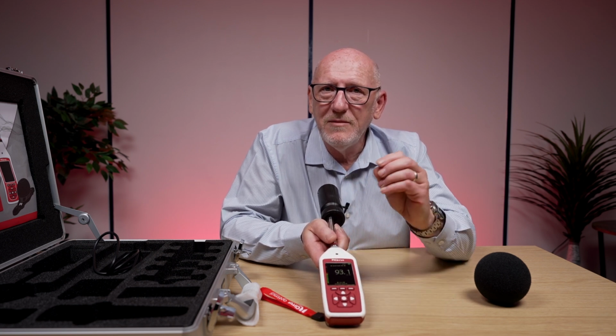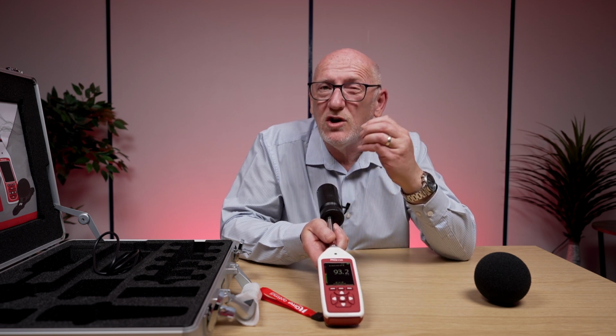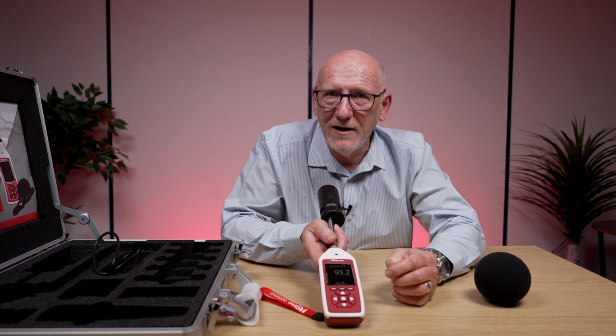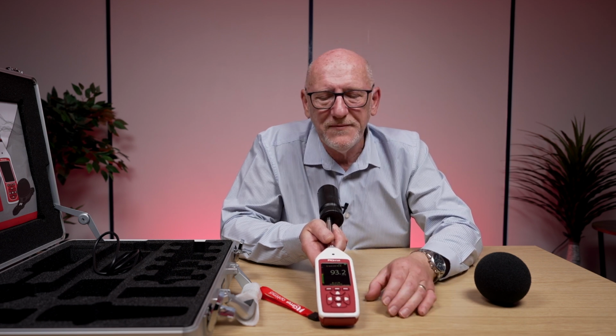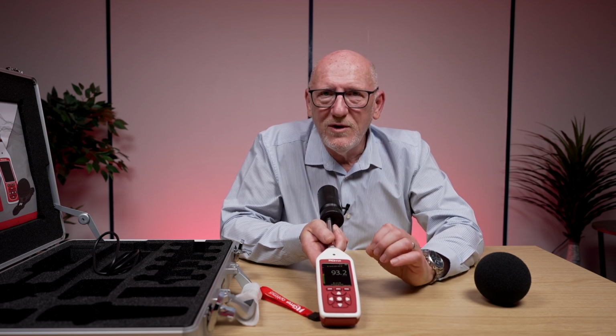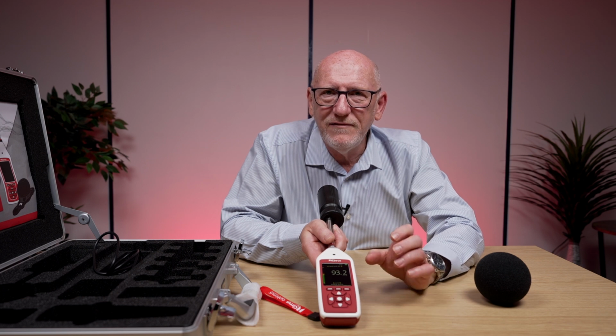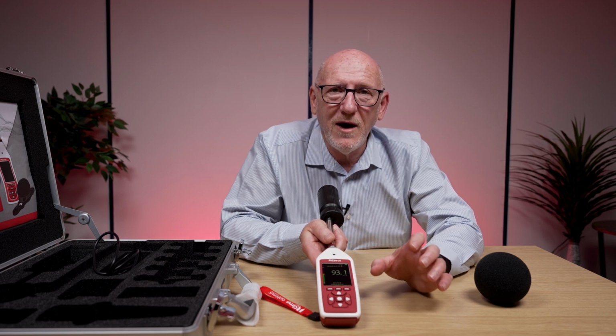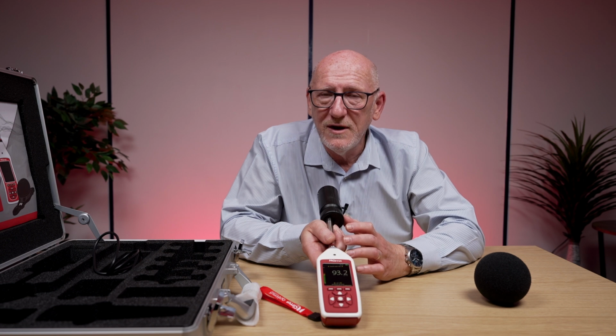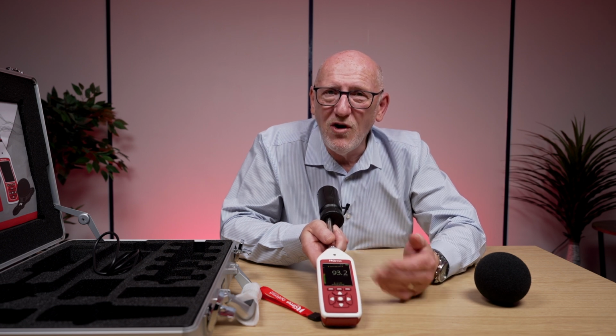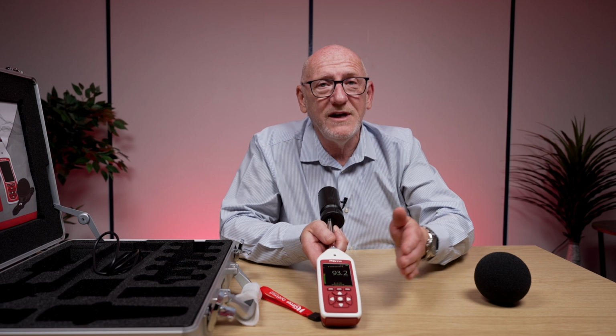So your Optimus Plus sound level meter is going to listen to that tone and make any adjustments automatically that it needs. But what it's also going to do is it's going to log that calibration value. And it's also going to log the adjustment that it's made, which is called the offset. It's usually point something of a decibel. When we were looking earlier at setting the date and time, it's very critical that you make sure the date and time are accurate before you do the calibration. And the reason for this is because of it logging the fact you've done a calibration. It's going to log the date and time that you've done the calibration, and so you need that to be accurate.